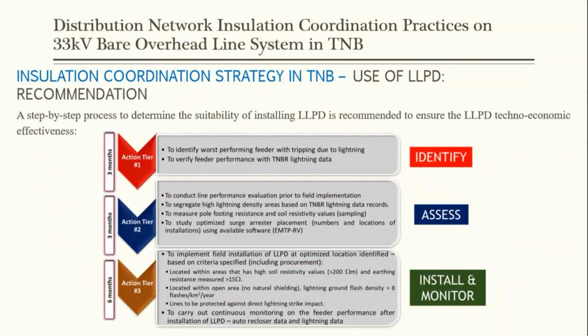And before we can use the LLPD, there is a certain step-by-step process to determine the suitability of installing the LLPD, and it is recommended to ensure the LLPD's techno-economic effectiveness. Okay, for the first 3 months, or action tier 1, we identify the WPF and verify it with the lightning data from TNB Research. For the next 3 months, or action tier 2, we assess. Assessment would be evaluation of the line performance in terms of the pole footing resistance, and also a study to optimize the placement of the LLPD.